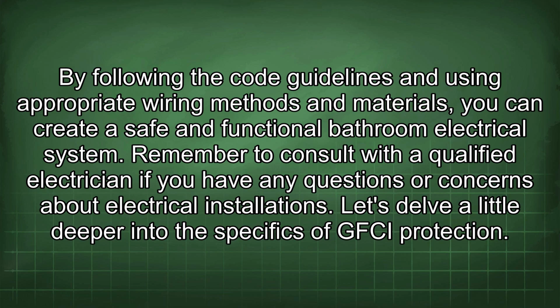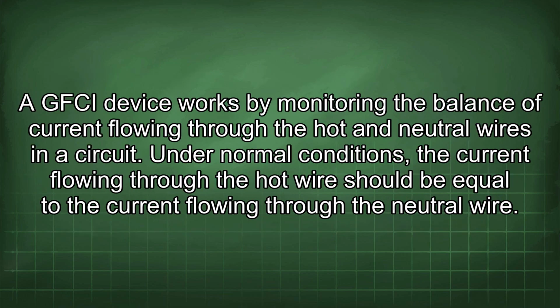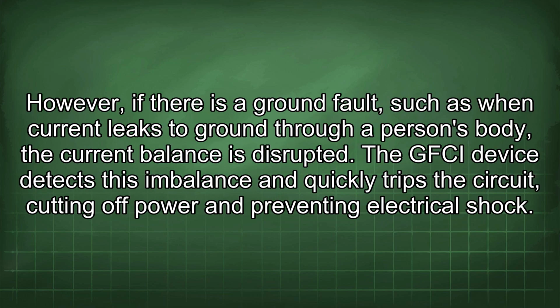Let's delve a little deeper into the specifics of GFCI protection. A GFCI device works by monitoring the balance of current flowing through the hot and neutral wires in a circuit. Under normal conditions, the current flowing through the hot wire should be equal to the current flowing through the neutral wire. However, if there is a ground fault, such as when current leaks to ground through a person's body, the current balance is disrupted.